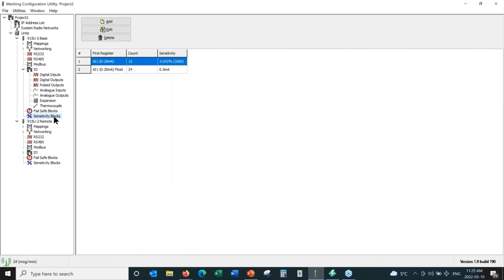Under serial expansion modules, we add thermocouple modules or other expansion I/O. Fail-safe blocks allow you to initialize registers so that upon power-up they are set with certain values, and if communications are lost, they go to a predetermined value. The sensitivity blocks — for example, analog input one — define how much the signal must change before transmitting. In this case it's set to 3% of 20 milliamps, which equates to half a milliamp. If this analog channel changes by more than half a milliamp, it transmits immediately.